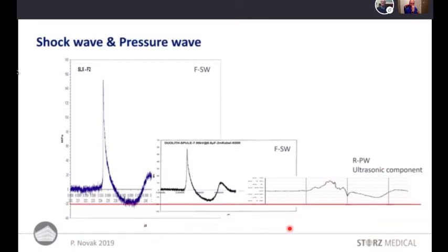So now we can put a line at 20 megapascal, where the cavitation starts to take place. We can see that lithotripsy is just in the range where this can happen, depending, of course, as I said, on impurities and diluted gas. With Duolith it is basically not possible, and with radial pressure waves it is not possible at all here.